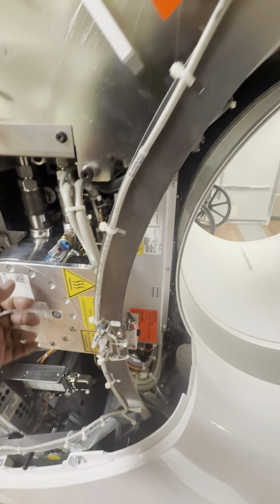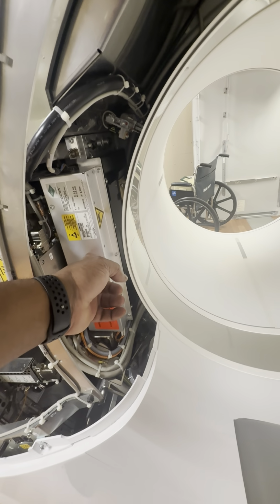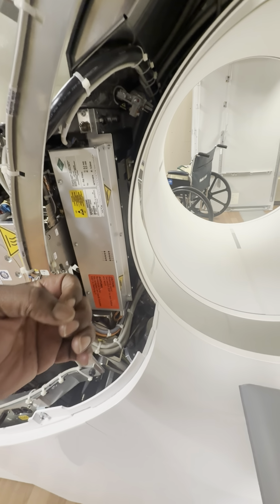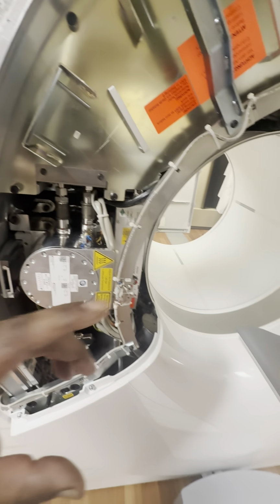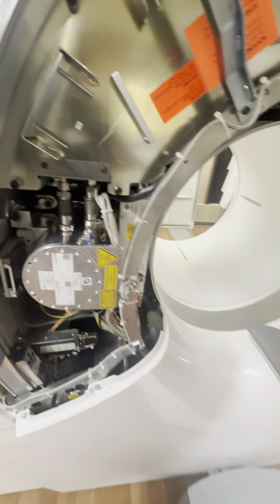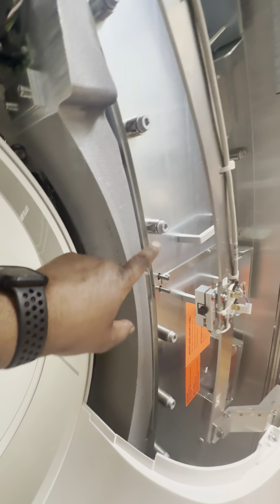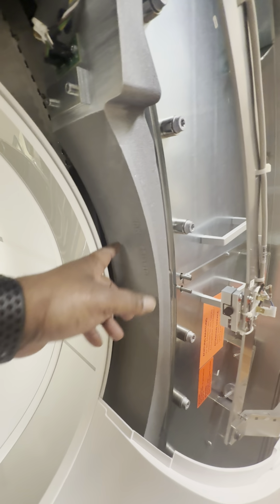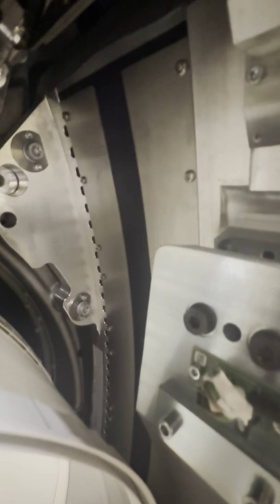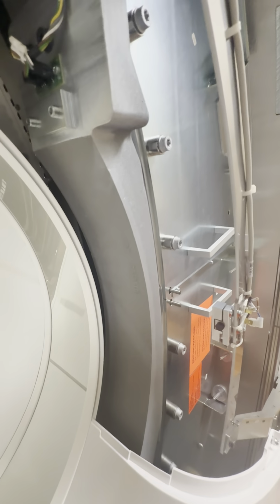So when you get a CT scan, this is the CT side. This is a tube. This is what produces the X-rays. It goes through this device right here called a collimator, which helps filter out how much radiation is pushed out. Now on this side, this is what receives the X-ray. This is your DMS. Right here, the black strip. That's what receives the X-rays as it spins around.